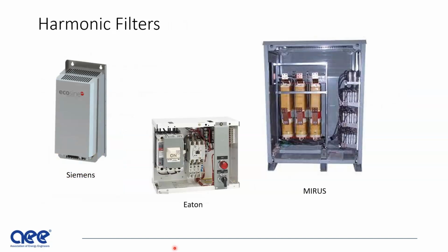When you buy these from Siemens, Eaton, or Mirus, these are active switchable harmonic filters that can properly address harmonic issues through their controls to detune the particular harmonics.